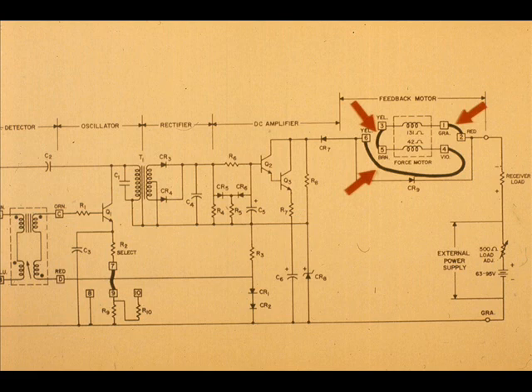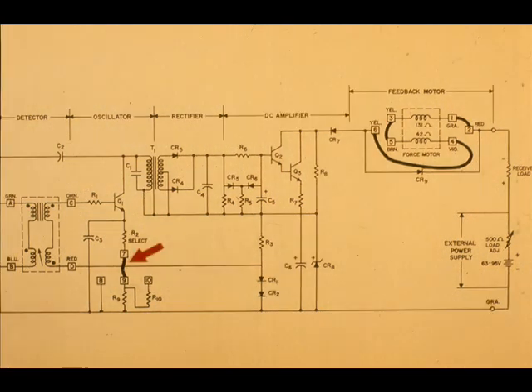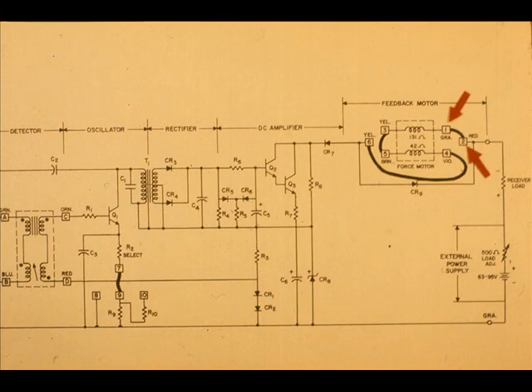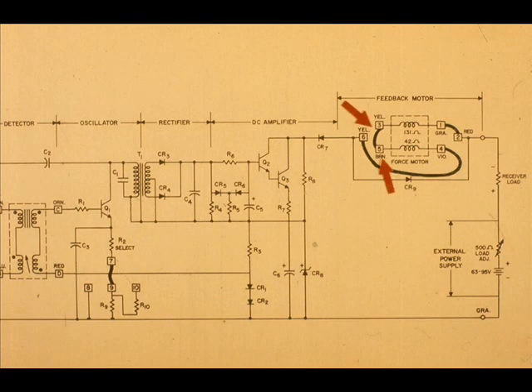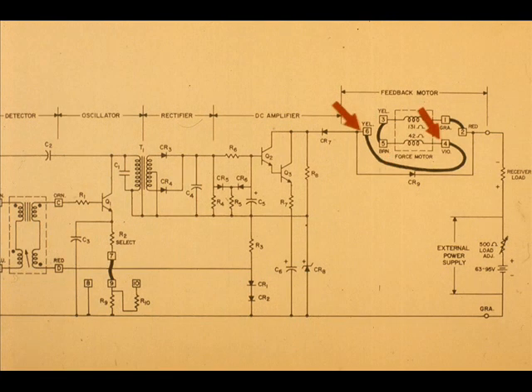Changing the links changes the net ampere turns of the force motor coil. The heavy lines represent the links. Note that one link is in the oscillator section. The link wiring shown here is for the medium spans. Follow the circuit from 2 to 1 to 3 to 5 to 4 to 6.